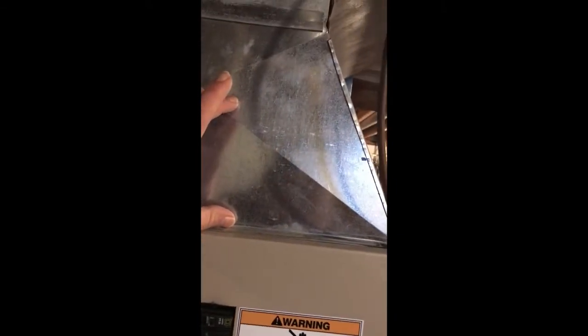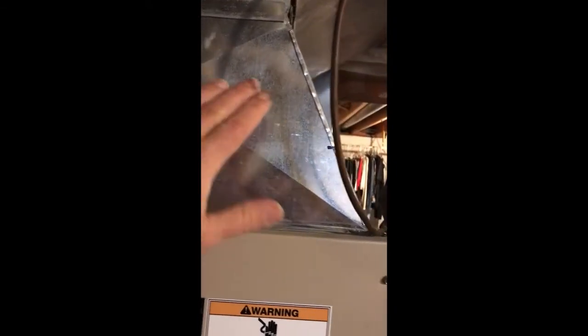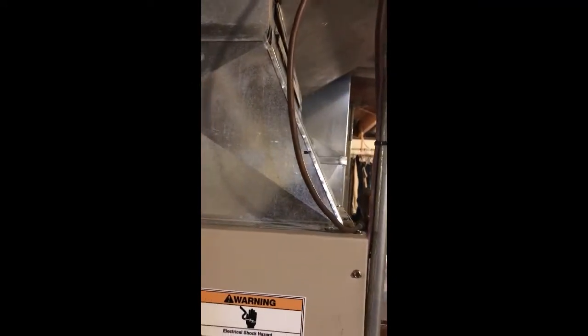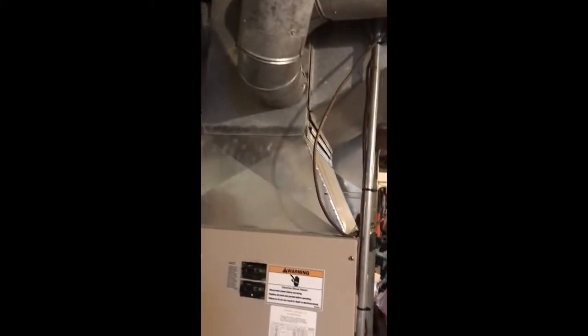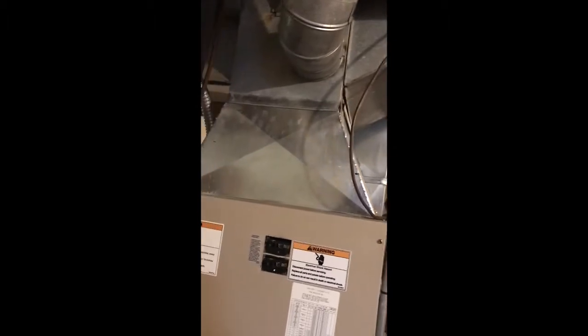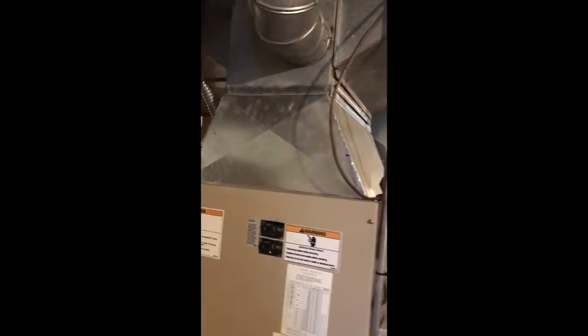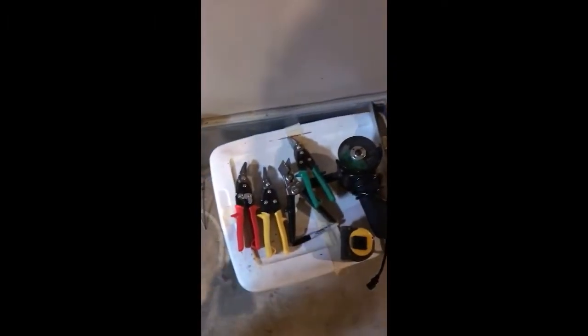So even though the hole underneath it coming off the coils is 12 by 15 or 12 by 12, the air still would blow in between this cavity far enough to still pass through the whole 12 by 24 heat exchanger, and hopefully there'll be enough heat going through our duct system that was designed for this 2,700 square foot house. So some of the tools I have, I'm going to attempt to do this with.